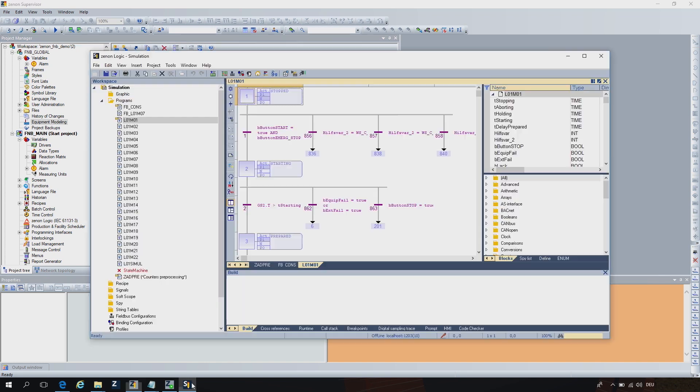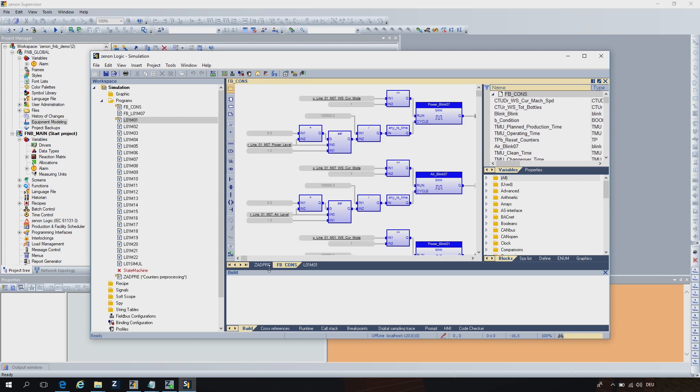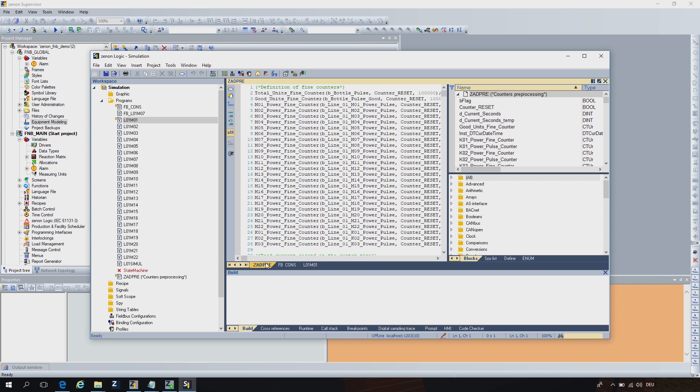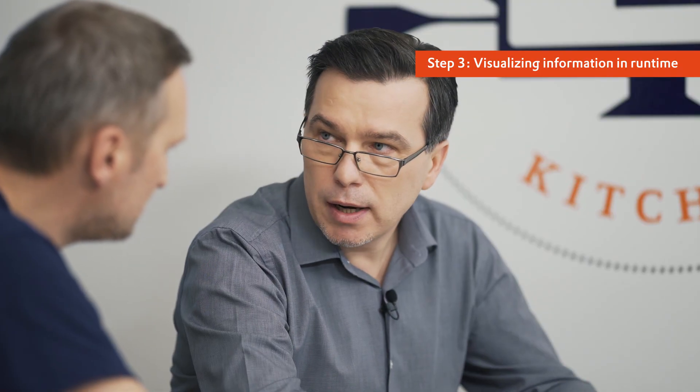The next step is what we do with the data. We have a powerful tool — different possibilities to process the data in real time. The one I like very much is zenon Logic, integrated fully in zenon Supervisor. Here you can use different kinds of programs and languages to process the data, to prepare counters, and to pre-process the data before you archive it. This can also reduce data amounts in the history, giving average values for example. You can correct errors in real time before bringing the data into the archive. A further step is to create and enable alarms and events, going from tags to alarms and events as a further piece of information, brought again into the contextualization.